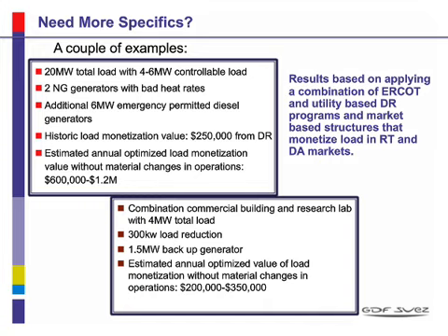To give you just a couple of examples, and I won't spend a lot of time on these, but I want to help people begin to see where I fit or don't fit in this equation. One customer was about a 20 megawatt total load, and they had two natural gas generators on site, but they had really bad heat rates. So they didn't run very often. People thought they were kind of nice for reliability, but they really don't give us much opportunity because the heat rates are so bad, they're so inefficient, and they're so old.